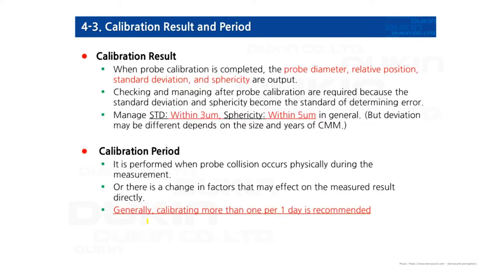So after calibration is done, the result will come up and you can see all those values, including probe diameter, relative position, standard deviation, and sphericity, which stands for form. So manage the standard deviation within 3 micrometers and sphericity within 5 micrometers in general. This means it can change under different circumstances, such as when the probe gets longer, bigger ball diameter, etc.